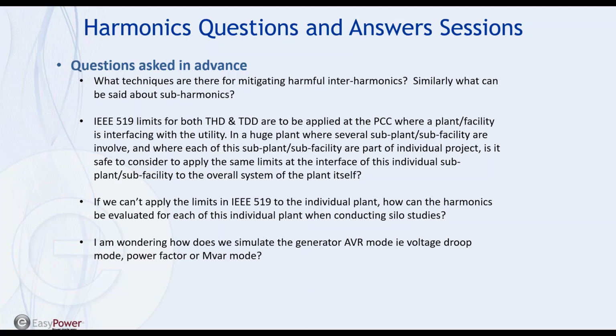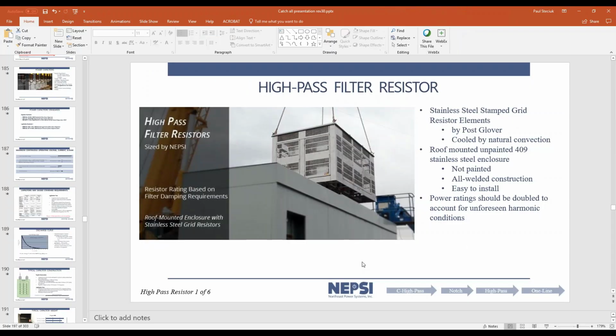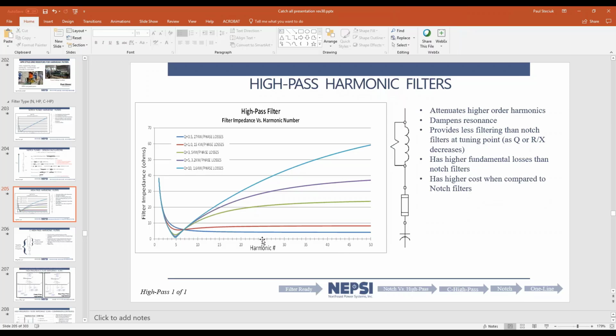There are some devices like cycloconverters that would put out a 5.5 or 6.0 or 6.5 harmonic. So we're talking about harmonics that occur at non-integer or non-typical values of harmonics. So the typical harmonics are 5th, 7th, 11th, 13th, 17th, 19th, and so on. Some devices do put out interharmonics that are of concern, and usually the technology that's used is to employ high pass harmonic filters and C high pass harmonic filters. And I will just put up a slide here real quick and show the high pass harmonic filter.